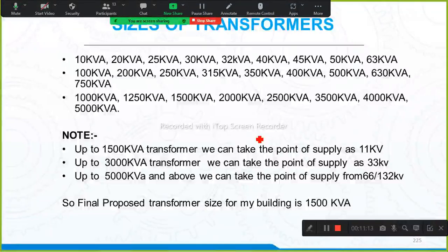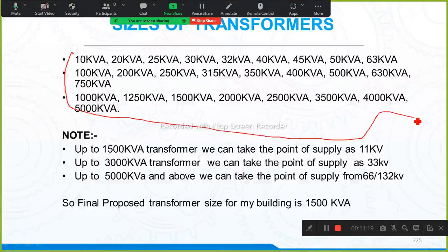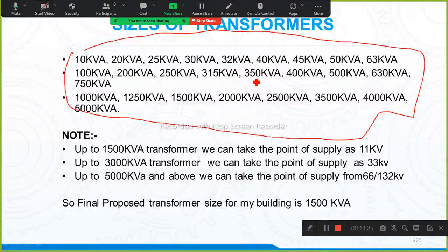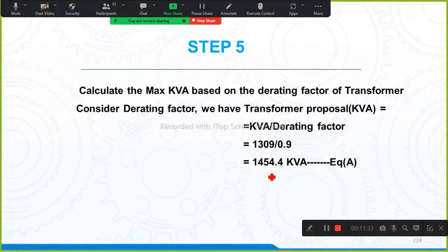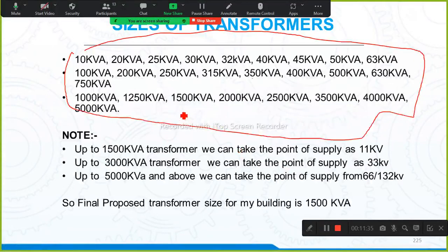No. We have directly 1250 and 1500 kVA transformers. These are the maximum availability sizes of the transformer in all the companies. Okay, we may have others apart from this also. Okay, some companies have 350, 320, like 340 kVA. But as I'm telling you, these are the sizes available with all the companies. Now, what is the size? We got 1454.4. So we need to take the approximate size. 1500 kVA is the transformer size available in the market.